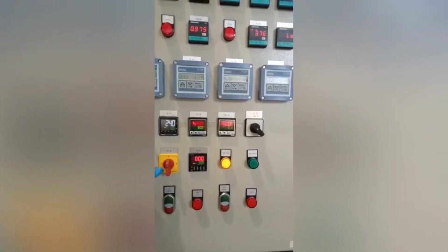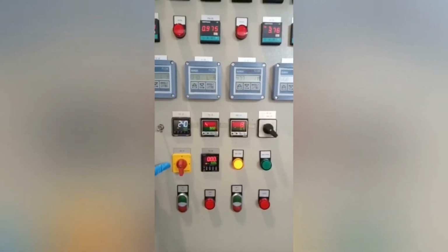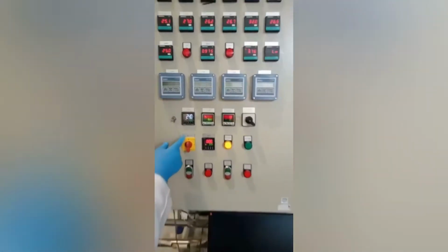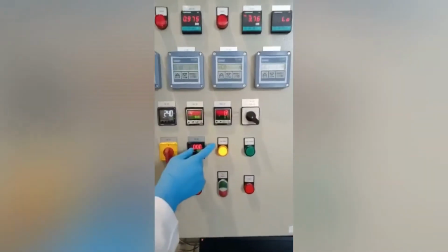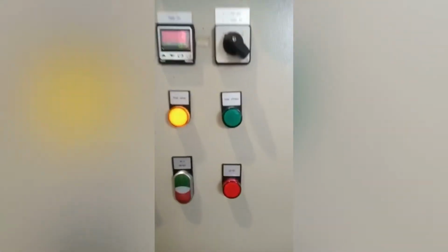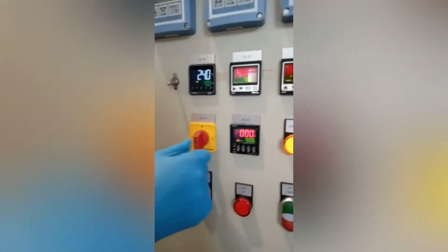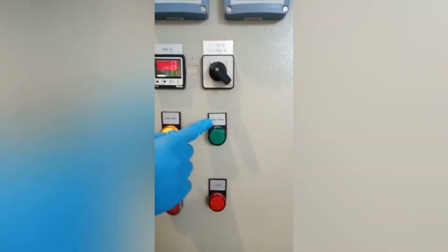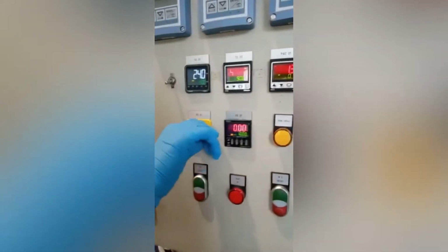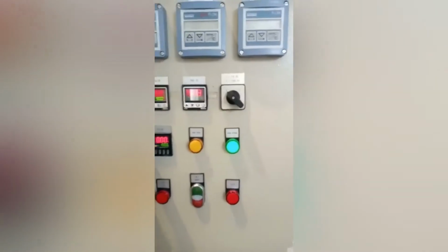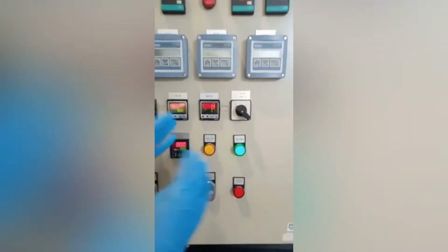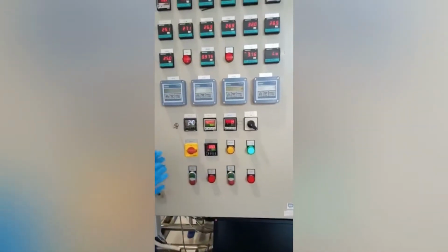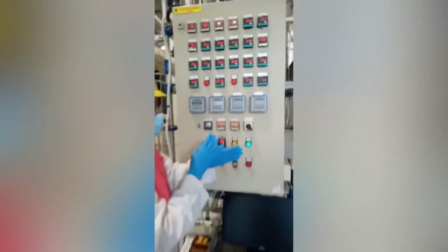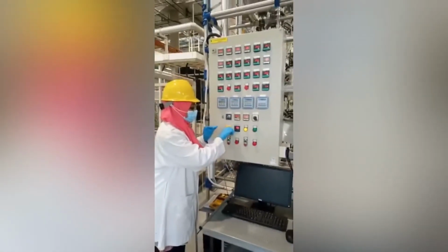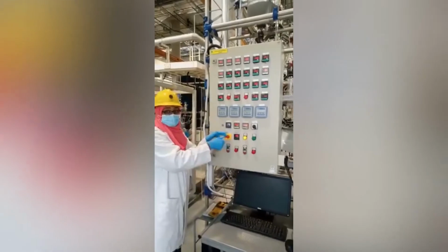Here we come to this main switch for the flux. When it's set at 0, it's total reflux. If I want to change it to total offtake, I switch it to 1, and I can maintain the flow between total reflux and total offtake by using number 2.